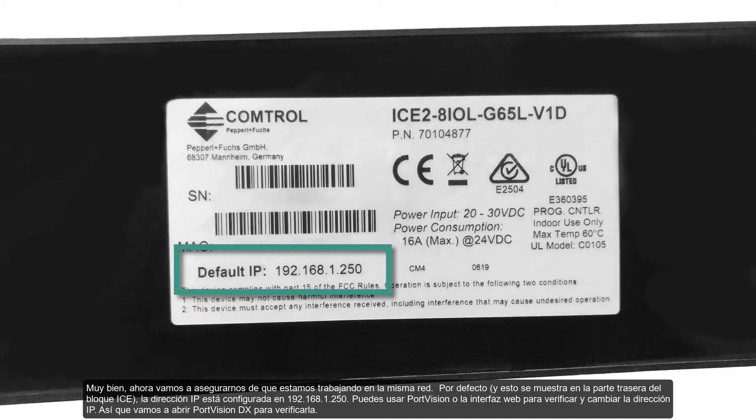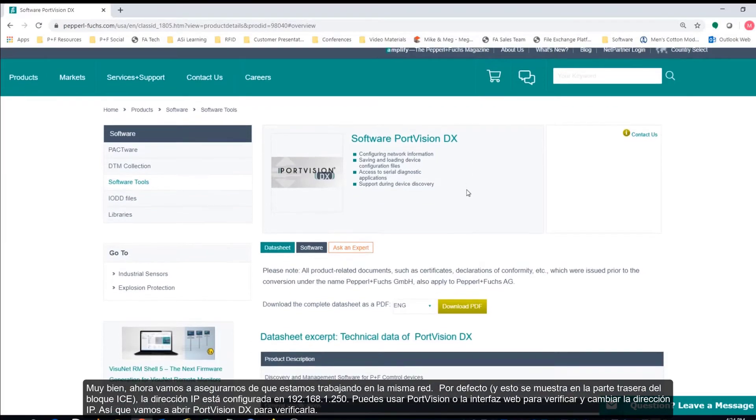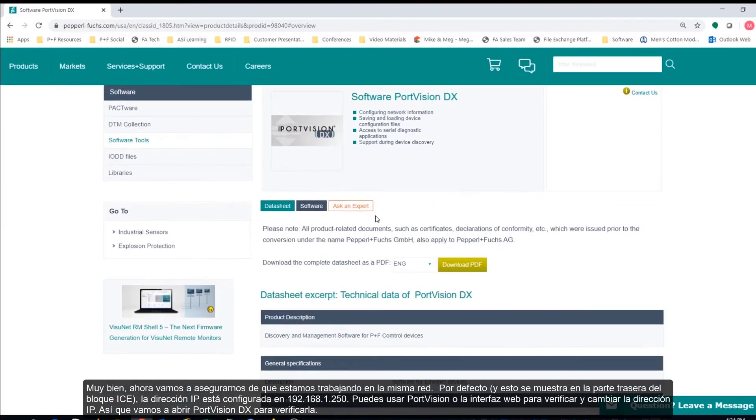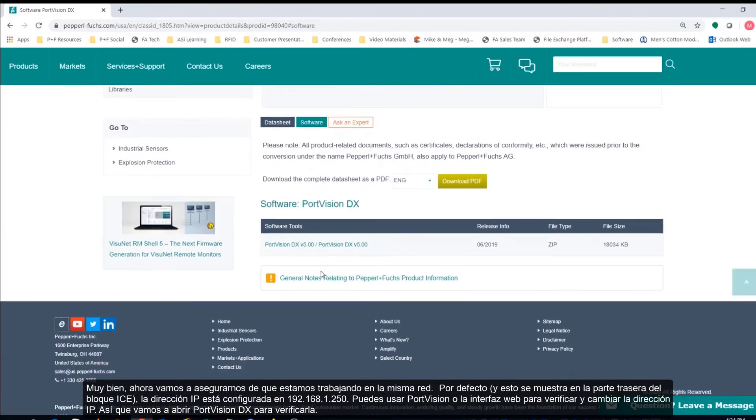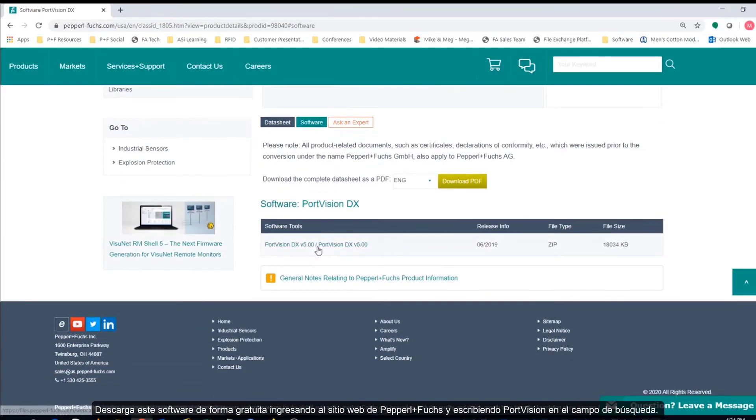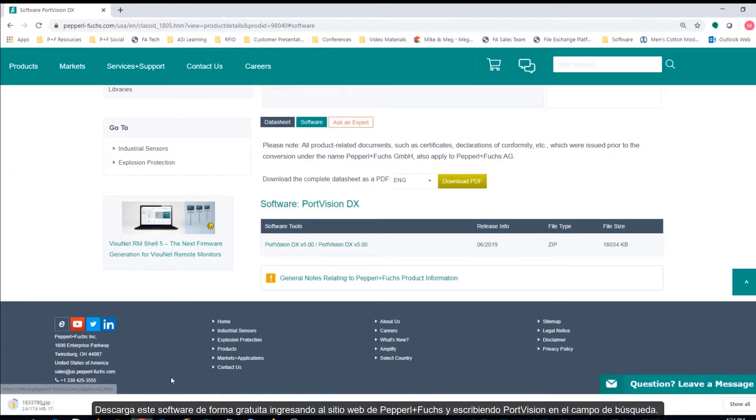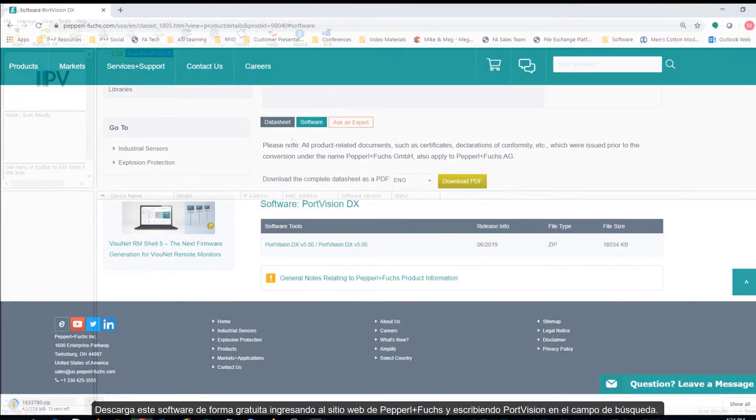Alright, so now let's make sure that we're working on the same network. By default, and this is shown on the back of the ICE block, the IP address is set to 192.168.1.250. You can use PortVision or the web interface to verify and change the IP address. So, let's open up PortVision DX to verify. Download this software for free by going to Pepperl & Fuchs website and typing PortVision into the search field.